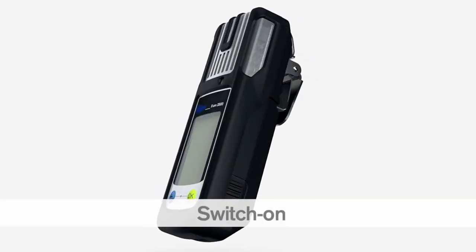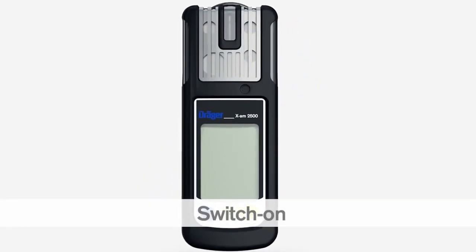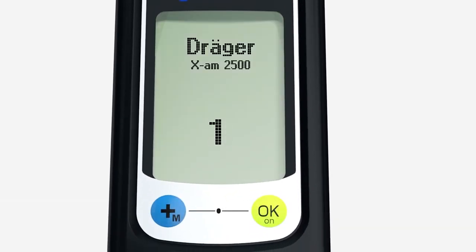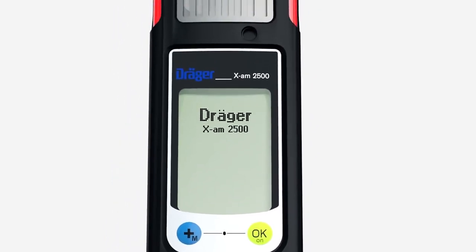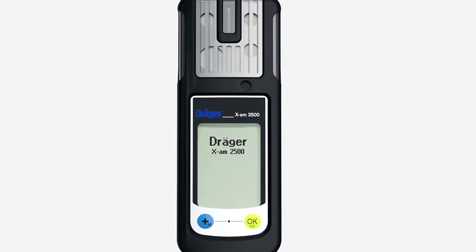To switch on the X-am 2500, press and hold the OK key for three seconds. A countdown is shown in the display. The LEDs flash and the vibration alarm vibrates to show that the device has been switched on. The instrument starts the boot sequence and performs an automatic self-test.